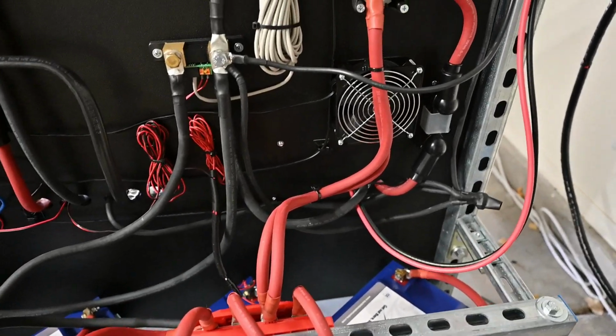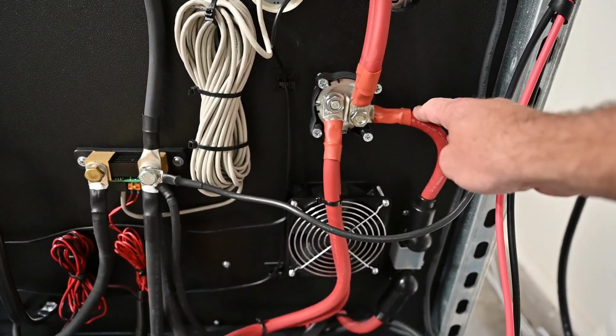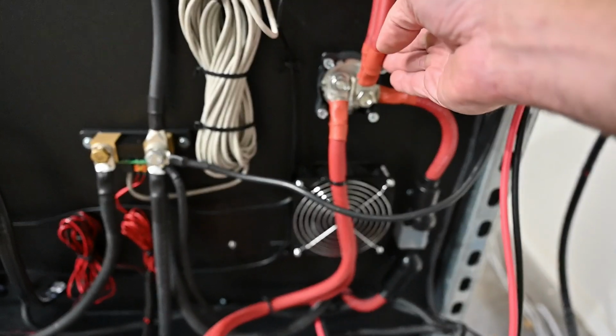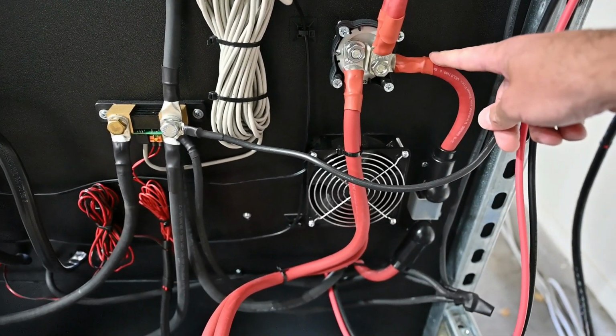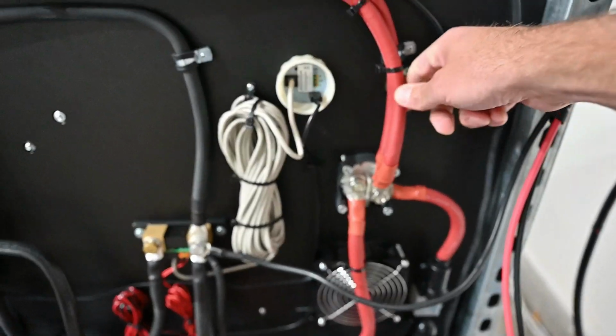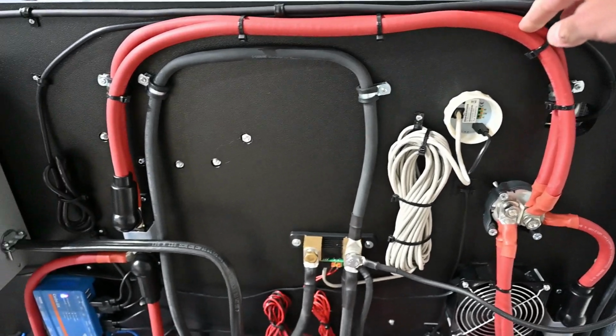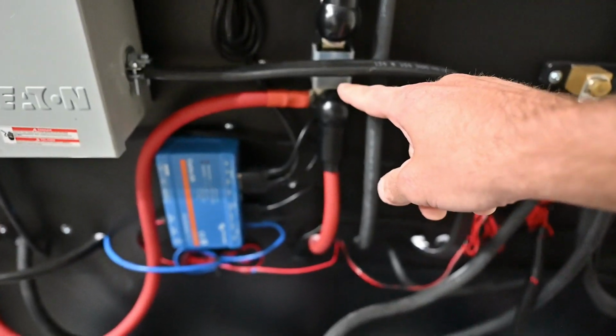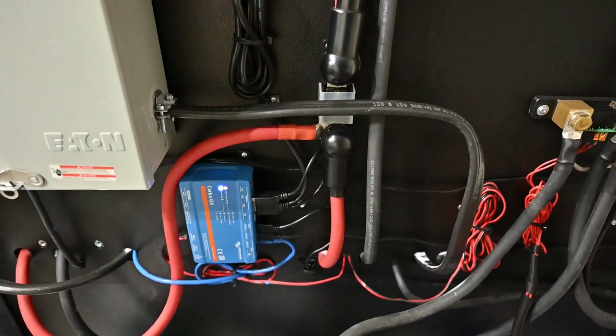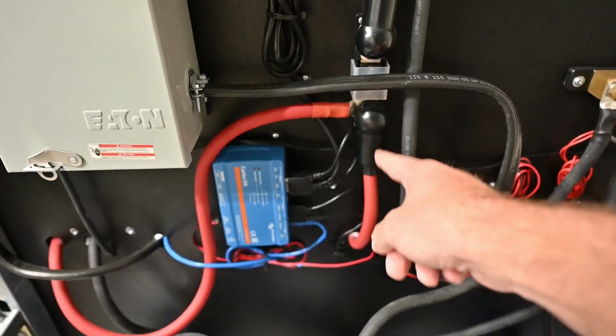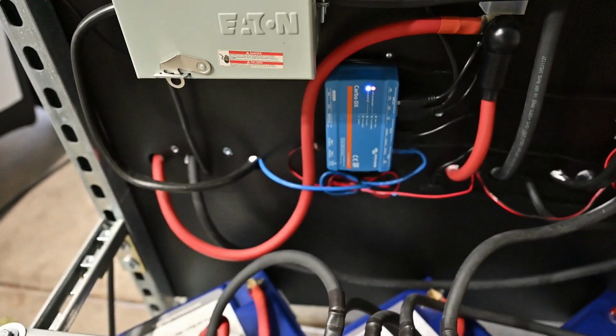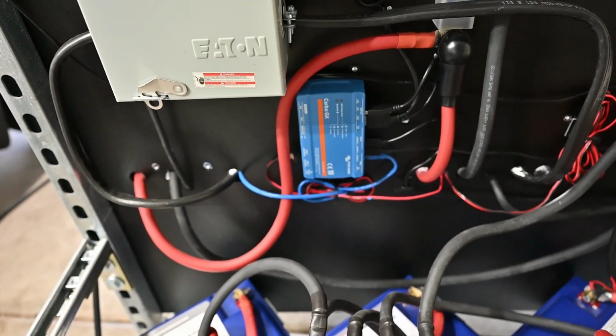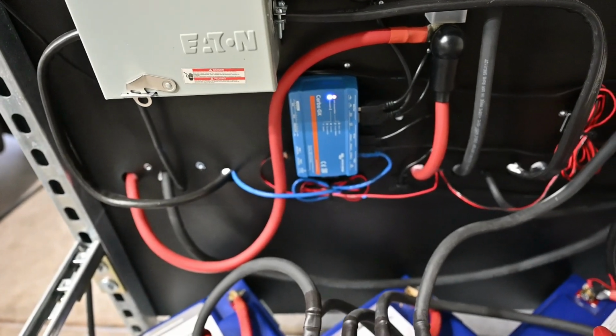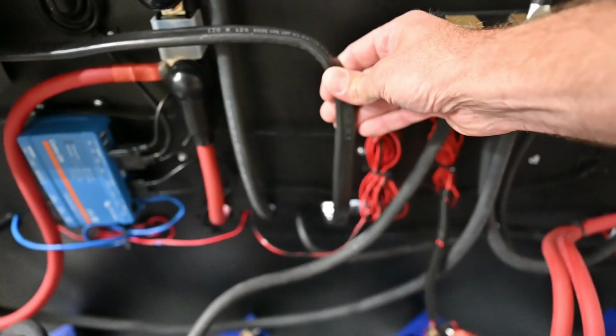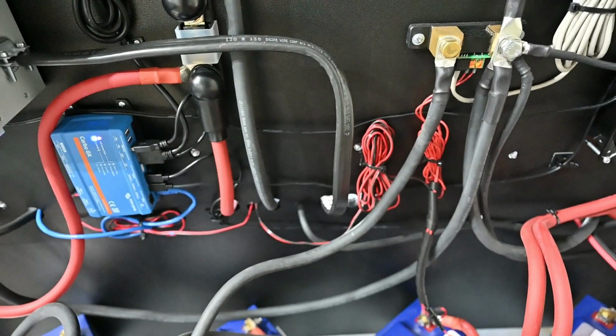Coming back to our main switch, the disconnect disconnects the batteries. From either the battery or the PV, there are two large 2-aught gauge cables that go into a single 250 amp fuse behind here, and out from those go power lines into the inverters. That's DC power going into the inverters, and coming out of the inverters is this very large AC wire.